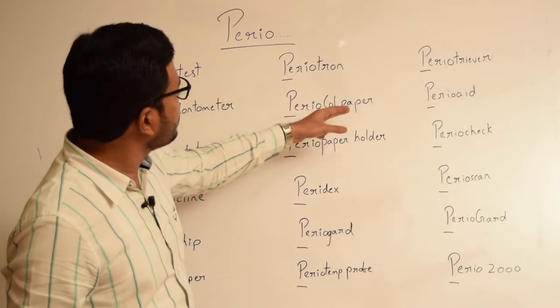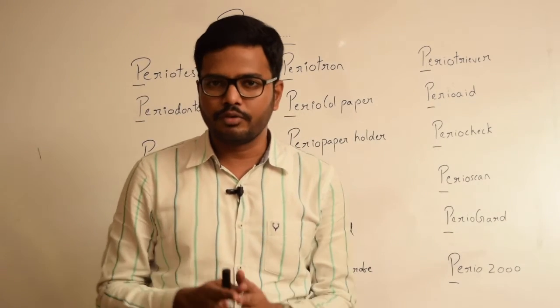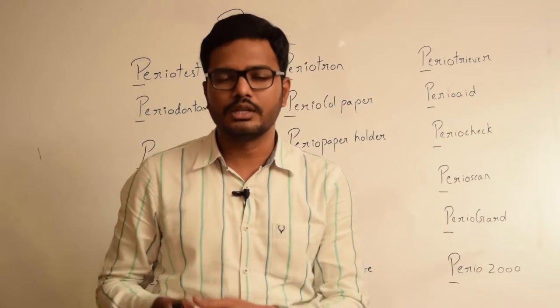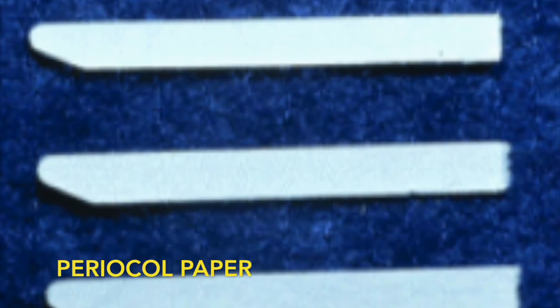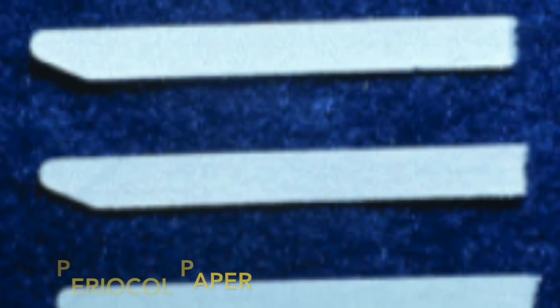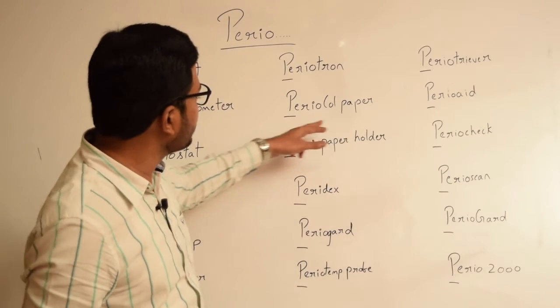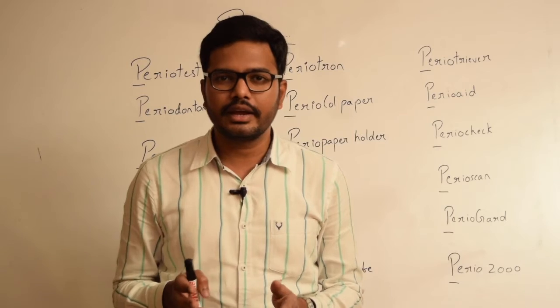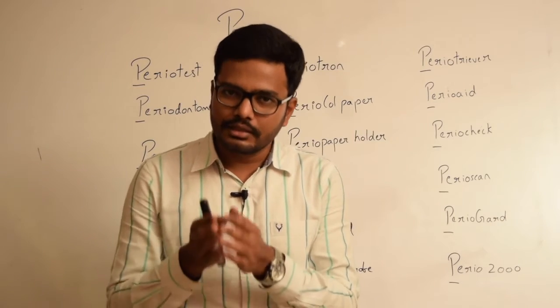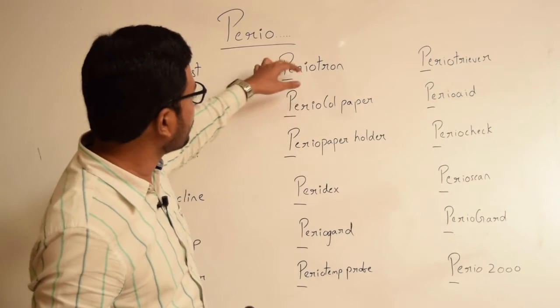Then we have periocol paper. In order to collect larger volumes of fluid in the range of 0 to 2 microlitres, periocol paper is used. And then we have periopaper holder, which, as the name indicates, holds periopaper. This holder can be mounted on all periotron models.